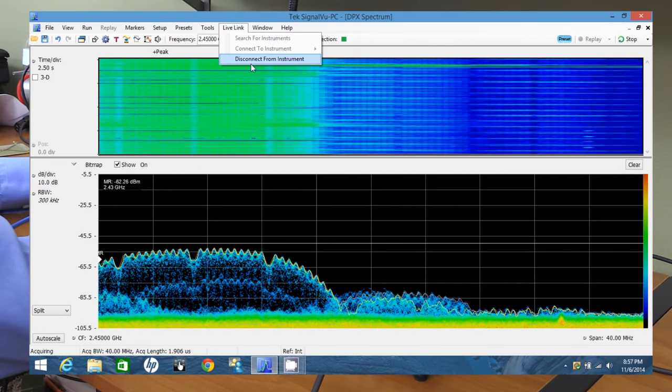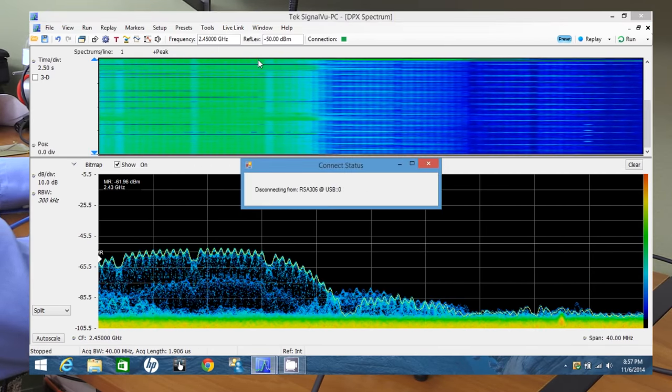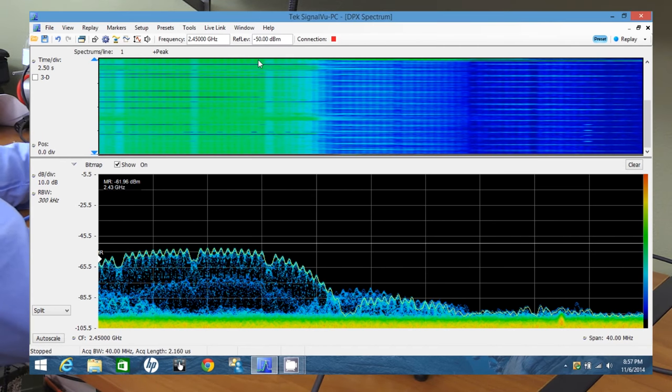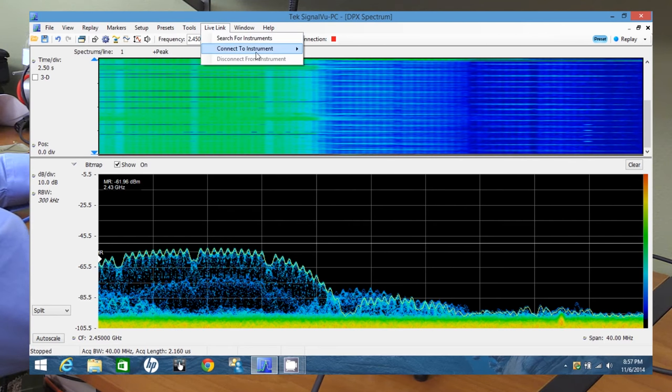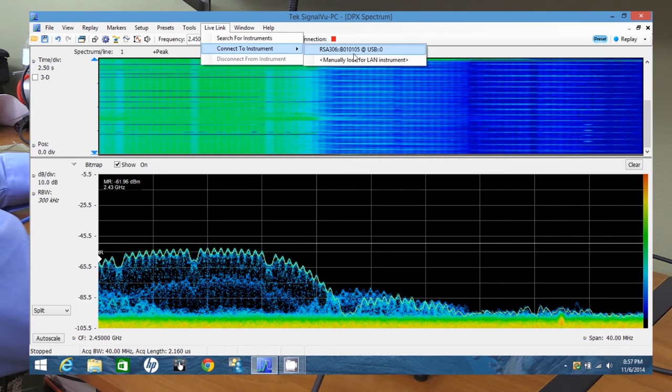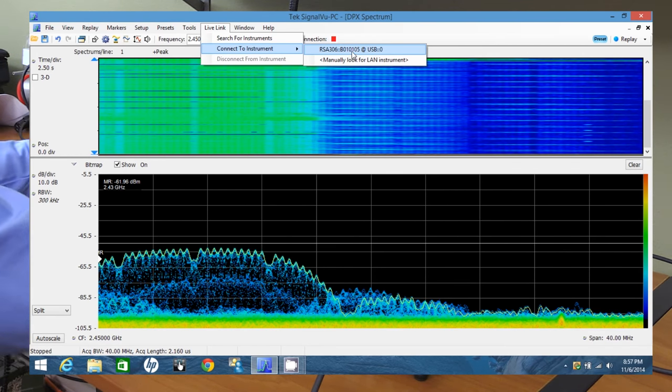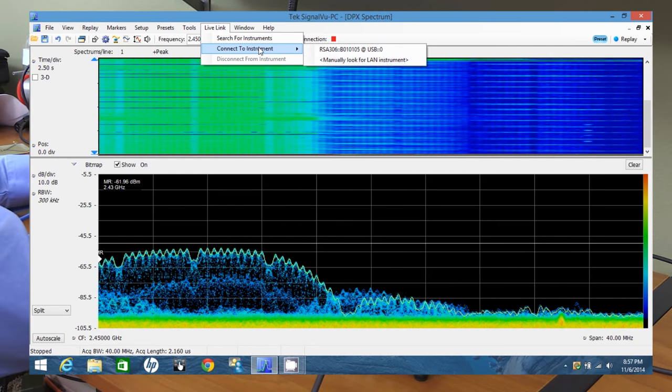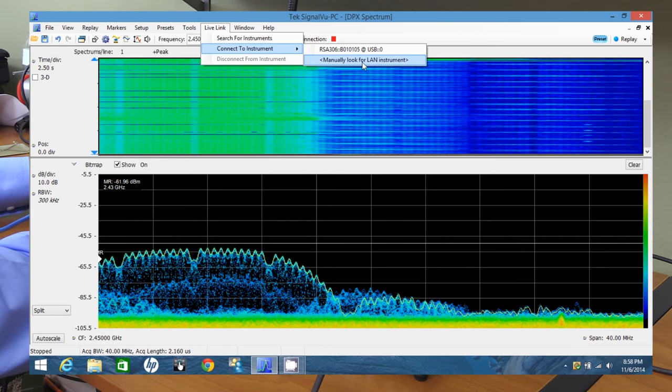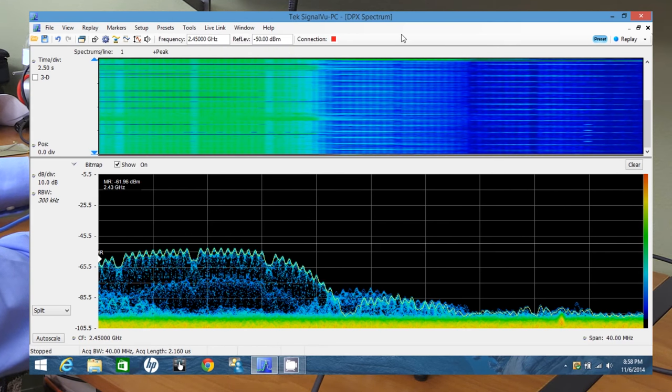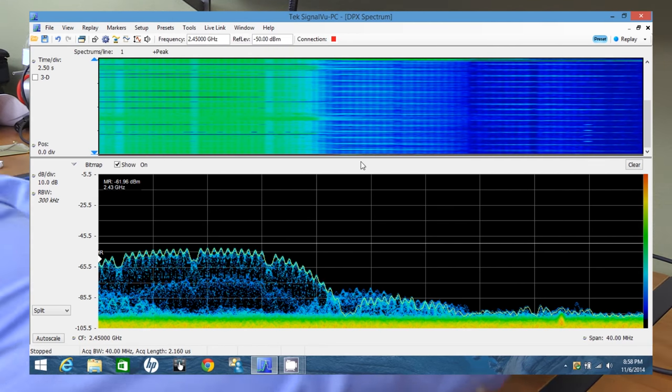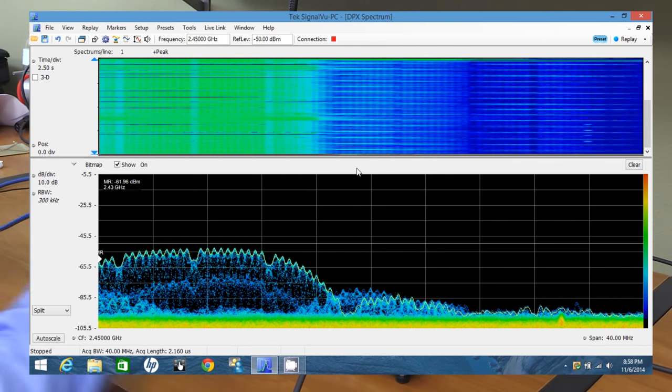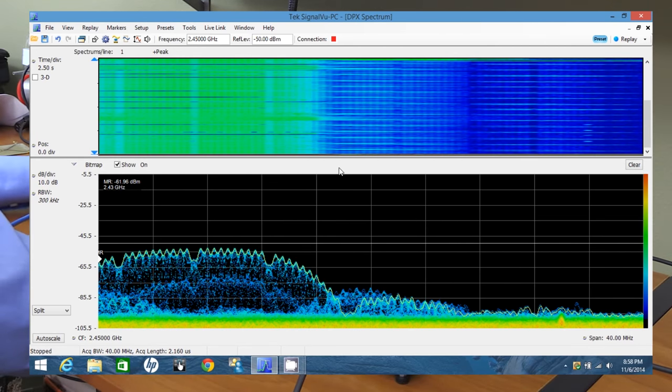Another thing is, if you disconnect from an instrument, and you have already had this instrument connected to your laptop beforehand or to your computer, you will find it in this list connect to instrument, it will list previous instruments on there. So if my MDO 4000 would have been on after I installed the software on this laptop, you would see the MDO 4000 listed in here too. And if for some odd reason, the search fails, especially on an ethernet device, you can click here and enter the IP address manually. Sometimes that's necessary. When I used a bunch of Wi-Fi extenders basically across the entire house, I needed to do that once, because I just didn't like the way I had it set up.